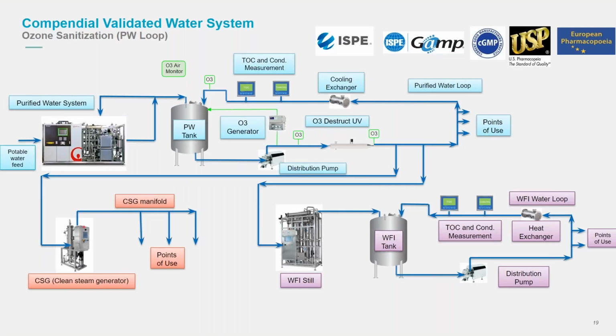And then when we look at an overall compendial water system where the WFI and purified water sits, this is a typical system for a site. We look at the purified water generation system at the front end, which is fed by potable water, which has to be drinking water standards in line with the guidelines. And then we make up purified water into purified water tanks. And then from that storage tank it is distributed around a distribution loop or a ring main. And at the end of the ring main is where you have your points of use. So this is the point where the water goes into production, into the product, and the customer uses that water at the right quality.